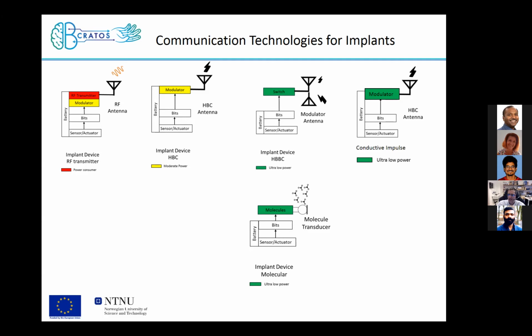And one of these that is well established is the RF technology. The use of RF for implants is not so efficient, as Pritam also mentioned, because the human body is a lossy medium for radio signals. Also, the electronics needed to generate radio signals for communication from the implant to external are very power consuming. Even if you use ultra low power devices to make high frequency and radio frequency oscillations, you need significant power.